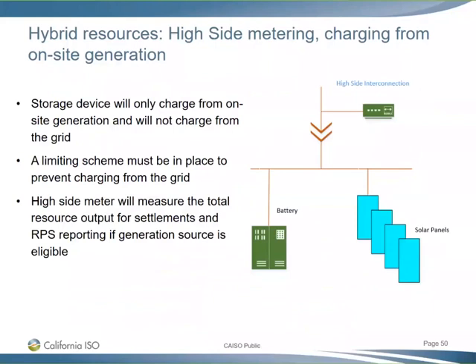The first is for a hybrid resource doing high-side metering, with the capability of charging from on-site generation. This means you can only charge the storage device from on-site generation, with a limiting scheme in place to prevent charging from the grid. The high-side meter, shown by the green box with dots at the top, on the high side of the transformer, measures resource output for settlements and any RPS reporting if it's an RPS-eligible resource.